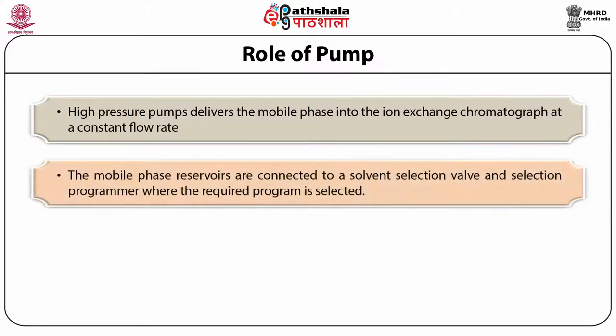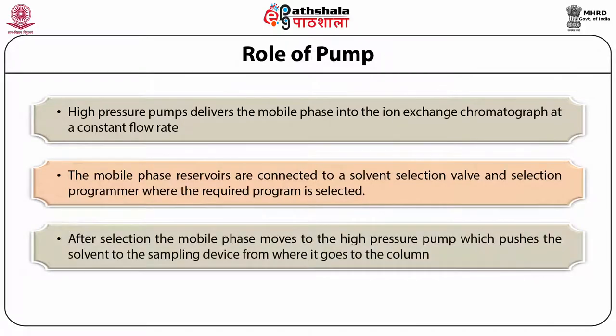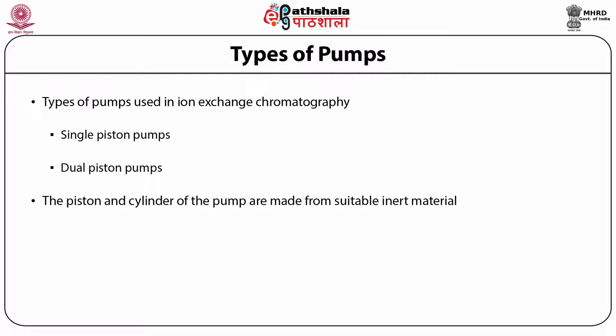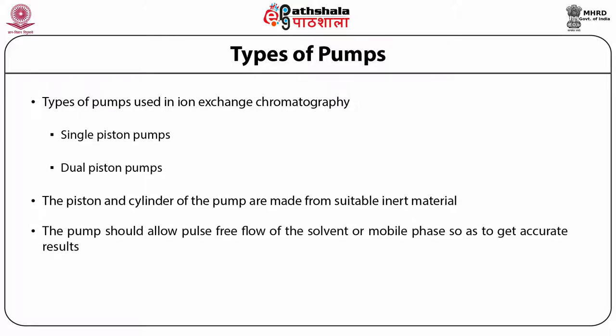The mobile phase reservoirs are connected to a solvent selection valve and a selection programmer. During the chromatographic procedure, we select a program according to our need, by which the solvents from the mobile phase reservoirs are selected and pushed to the sampling device, from where it goes to the Ion Exchange column. The pumps used in Ion Exchange Chromatography can be either single piston or dual piston pumps. The piston and cylinder used in the pump are made from inert material, because the mobile phase used in Ion Exchange Chromatography contains ions which can be corrosive.